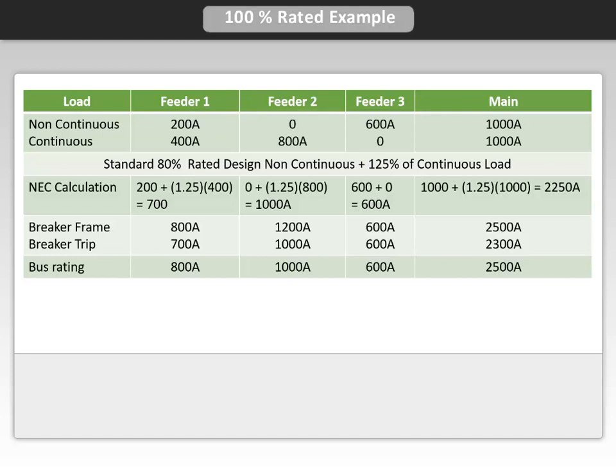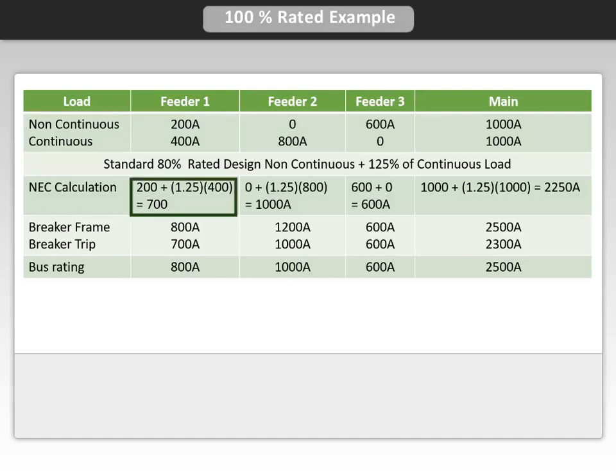Feeder number 1 has a non-continuous load of 200 amps plus a continuous load of 400 amps. The NEC requirement for sizing continuous loads is: we take 400 amps times 1.25, plus the 200 amp non-continuous load, and the total is 700 amps.